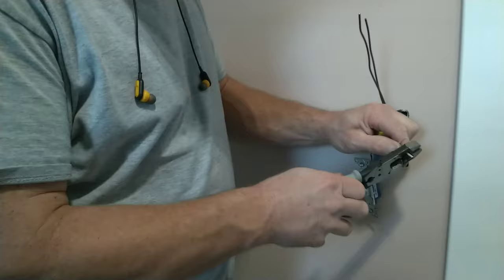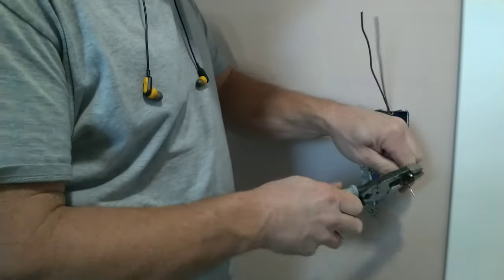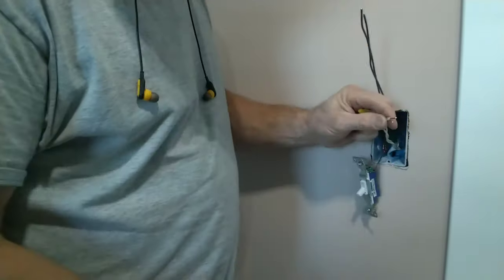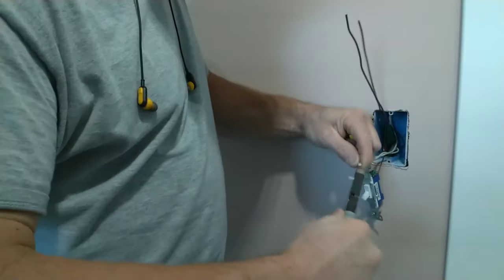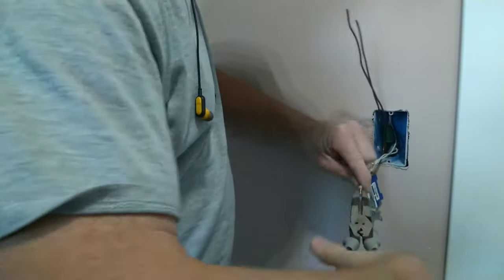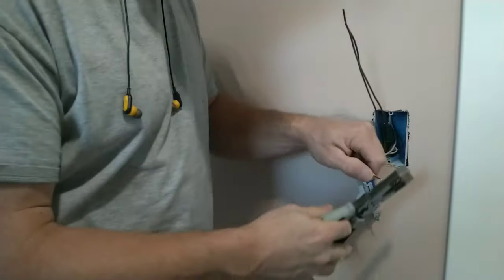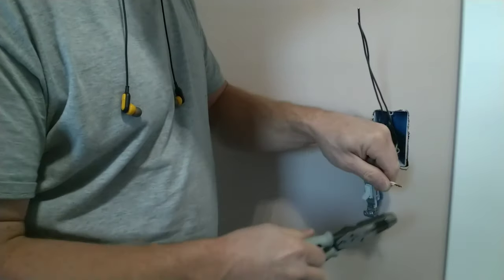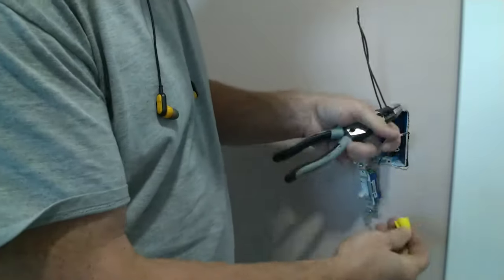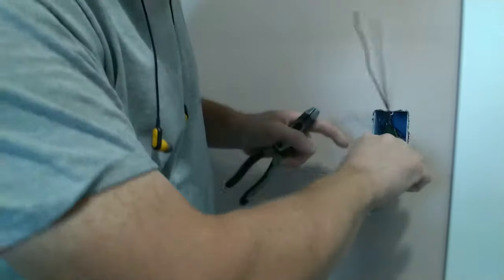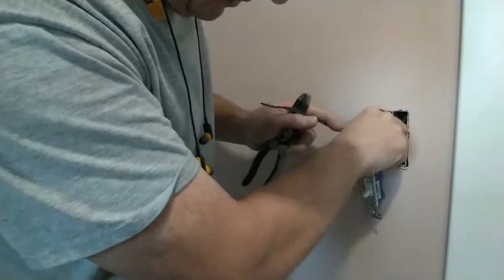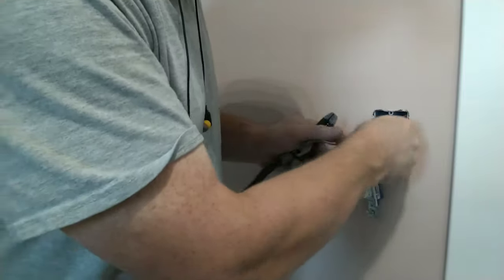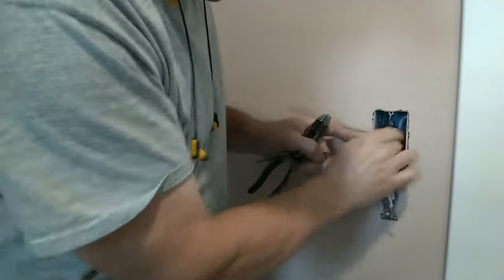Now in stripping this, I do about 7/8 to 1 inch of strip on both of these. Line them up, put them together, put your linemans on, and I twist them in that fashion. And then I cut them off so I've got approximately 1/2 inch to 5/8 of reveal left. You put your wire nut on it, take your wire, no folds, you want nice radiuses, to the back of the box, and tuck that wire in.